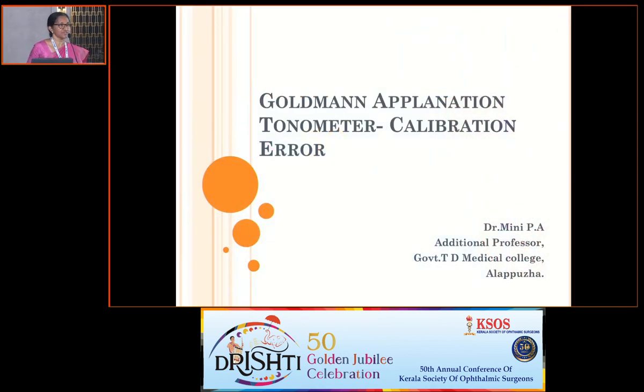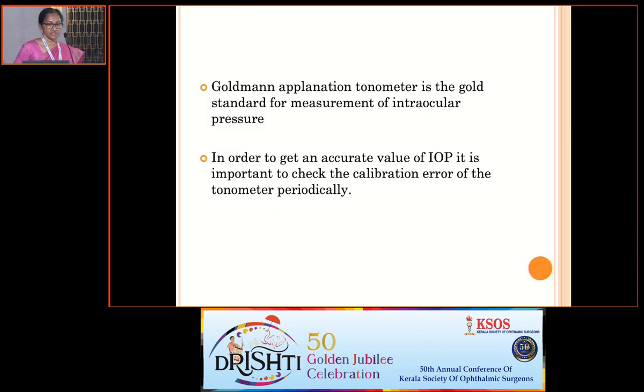Good afternoon. An accurate measurement of intraocular pressure is important in the management of glaucoma. So, even though various tonometers are available for measurement of intraocular pressure, Goldmann Applanation tonometer is the gold standard and is the most widely used one. To get an accurate measurement with this tonometer, it is important to check the calibration error of the instrument periodically. So let us see how to check the calibration error of Goldmann Applanation tonometer.